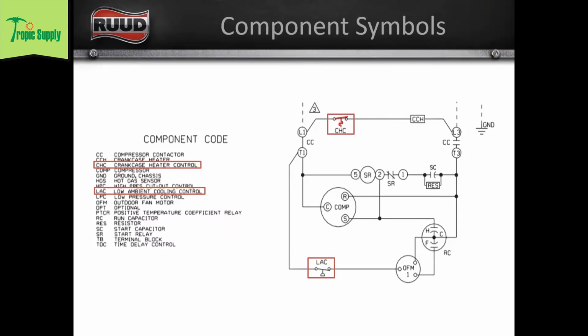Can you replace a single pole contactor with a double pole? Well, can you? Yes. The reason that you don't, and the reason that a lot of times they're used in equipment, is because the single pole allows us to have electrical potential going through the windings in our compressor, and that does generate a little bit of heat. So a lot of times that's used as off-cycle crankcase heat. So I always recommend going back in with OEM parts and with the same type of device. But that's one of the reasons that a single pole contactor might be used.